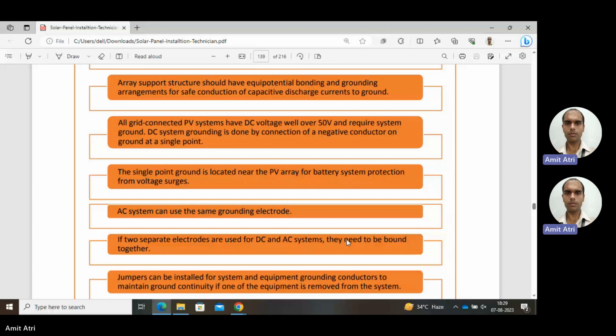Okay, next. All grid connected PV systems have DC voltage well over 50 volt and require system ground. So DC system grounding is done by connection of a negative conductor to ground at a single point. Basically the PV system is generating the voltage, and the voltage level taken is 50 volt, so they require proper grounding. Next, the single point ground is located near the PV array for battery system protection from voltage surges. Surges are a sudden hike in the voltage. So this high voltage should not reach the battery. We protect the battery from this voltage surge, so there should be a grounding provided there to protect the battery system.